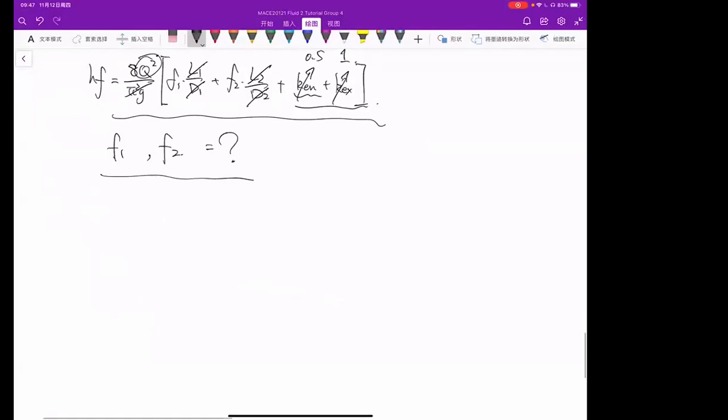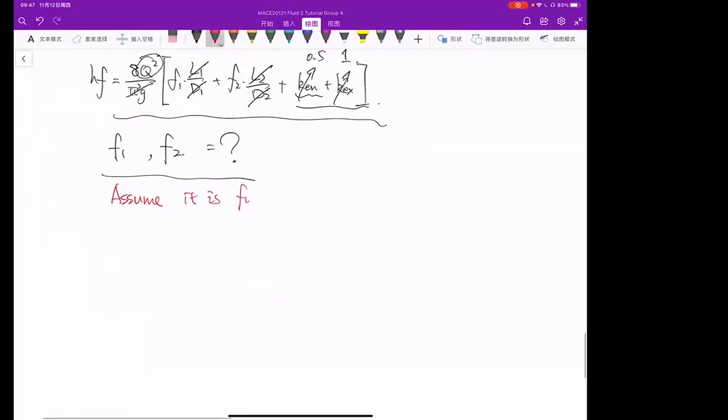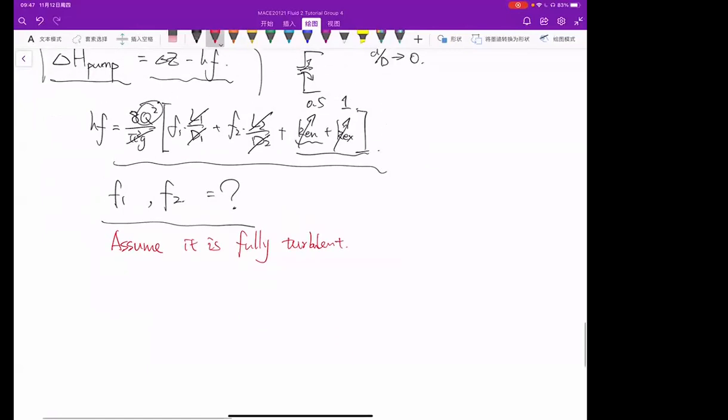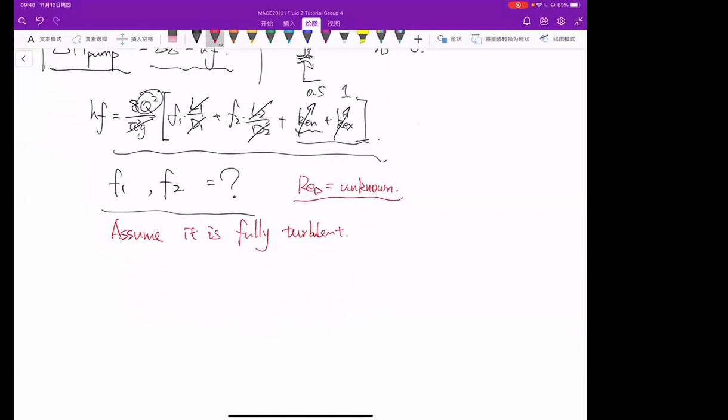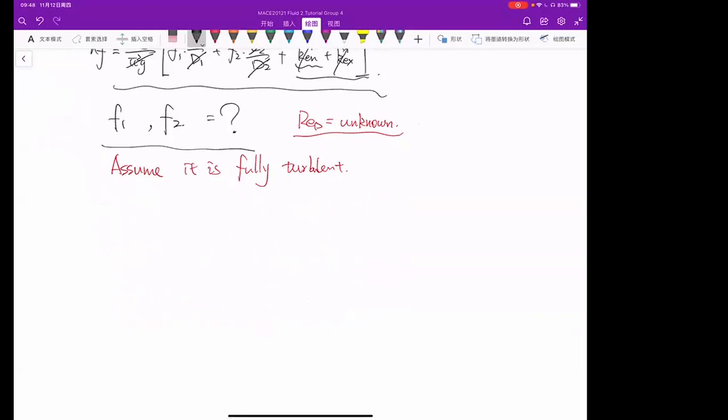So here's a trick. We should assume it is fully turbulent, since in this scenario you don't have flow rate, you don't have velocity. That means you cannot calculate the Reynolds number. Without the Reynolds number, you cannot find a corresponding friction factor on the Moody chart.